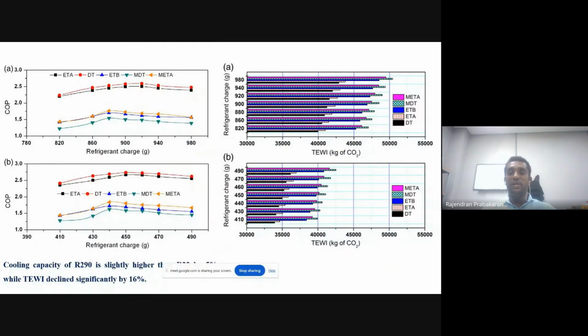Similarly for the TEWI analysis, there are two categories, direct and indirect: one is emission caused by the compressor power consumption from the grids, and the other is CO2 emission caused by the refrigerant usage and refrigerant leakages from the system. This indicates a 16% decline in the TEWI. So both these studies showed that R290 is much better in retrofitting applications.